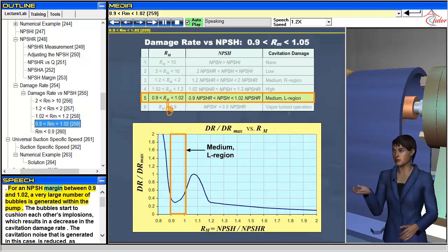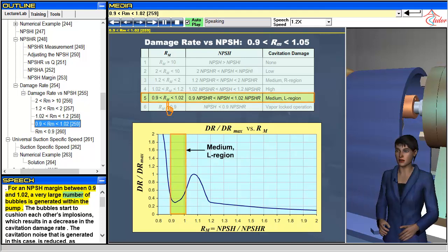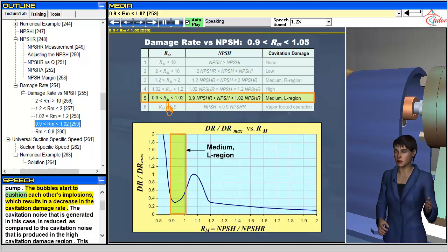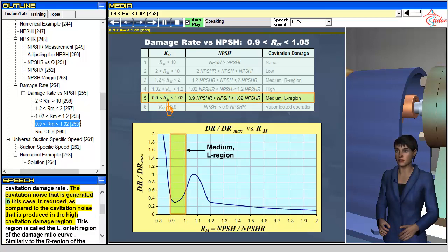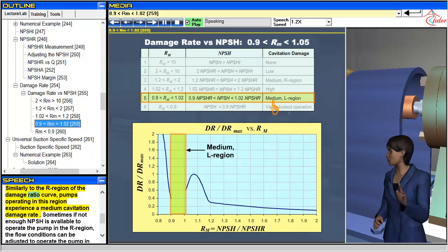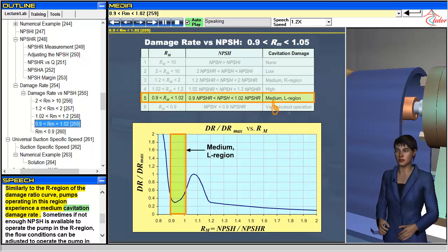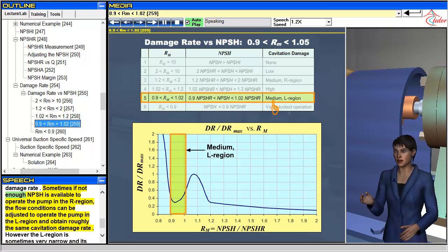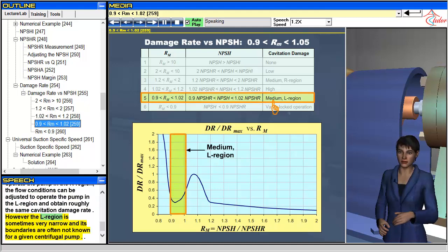For an NPSH margin between 0.9 and 1.02, a very large number of bubbles is generated within the pump. The bubbles start to cushion each other's implosions, resulting in a decrease in the cavitation damage rate, and the cavitation noise is reduced compared to the high cavitation damage region. This region is called the L, or left region of the damage ratio curve, and similarly to the R region, pumps operating here experience a medium cavitation damage rate. Sometimes, if not enough NPSH is available to operate in the R region, flow conditions can be adjusted to operate in the L region, though this region is sometimes very narrow and its boundaries are often not known for a given pump.